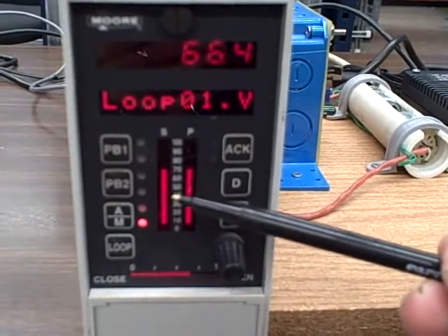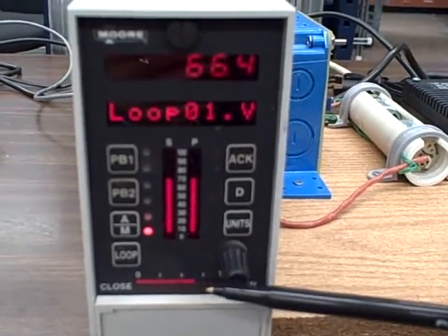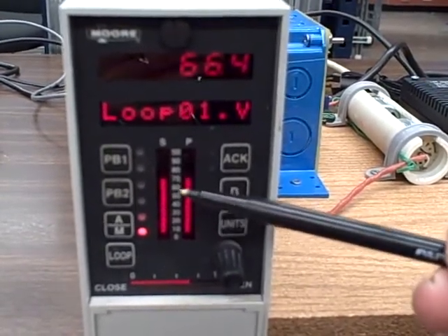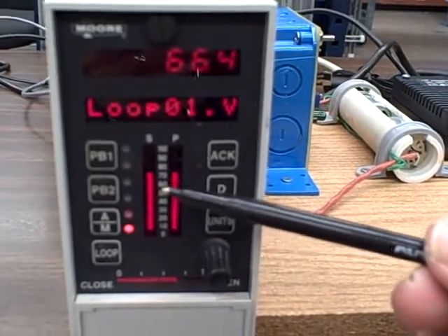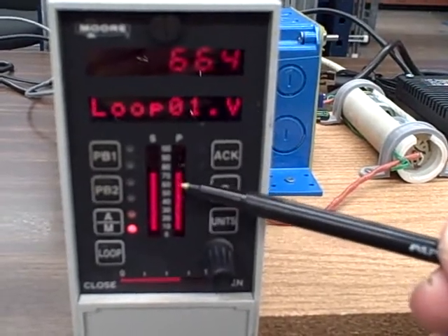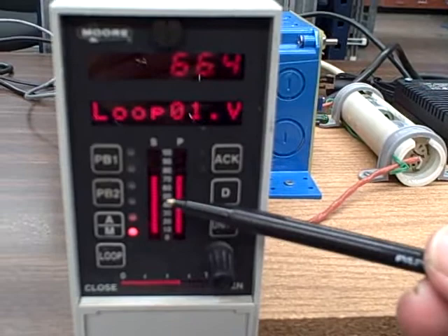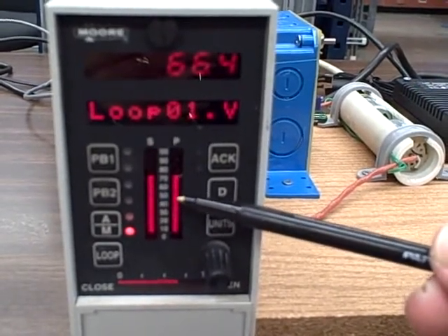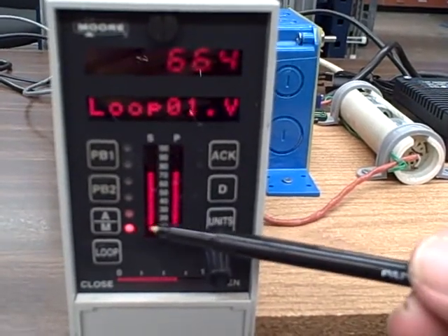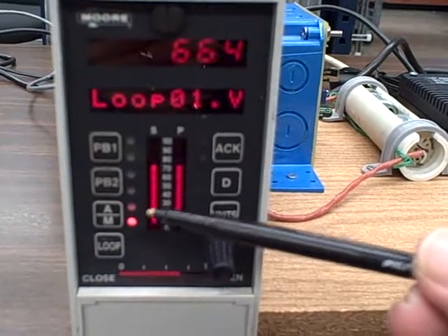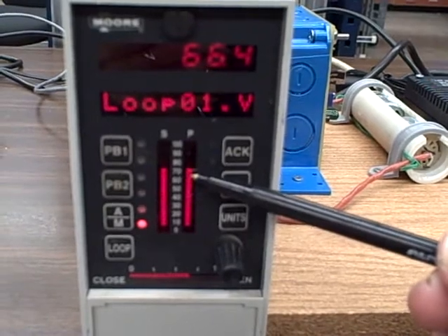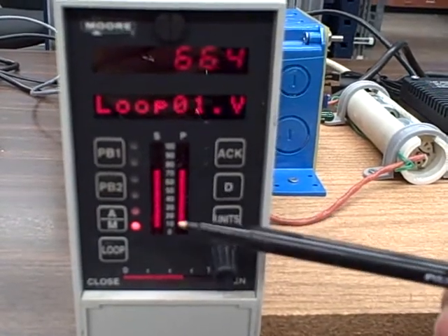If we did not have set point tracking, what would happen in manual mode, as I raise and lower the output, is we would see a change in the process variable, but the set point would remain fixed at whatever level we last left it. That would mean, potentially, that after adjusting the process and having the process variable be at some value, switching to automatic mode may leave me in a condition where the set point and process variable don't match, in which case the controller would begin to correct and try to get me to set point. So the idea of set point tracking is based on the assumption that in manual mode I'm adjusting the process variable to a point where I want it to be prior to switching to auto, and so they make the set point track it.